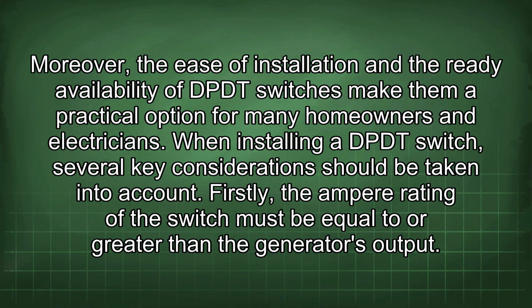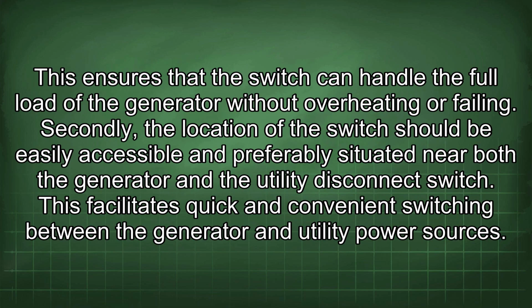Firstly, the ampere rating of the switch must be equal to or greater than the generator's output. This ensures that the switch can handle the full load of the generator without overheating or failing. Secondly, the location of the switch should be easily accessible and preferably situated near both the generator and the utility disconnect switch. This facilitates quick and convenient switching between the generator and utility power sources.